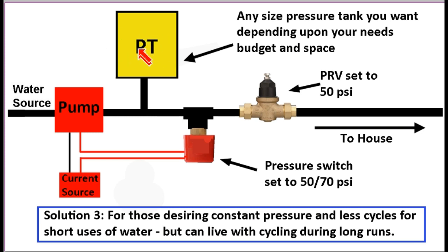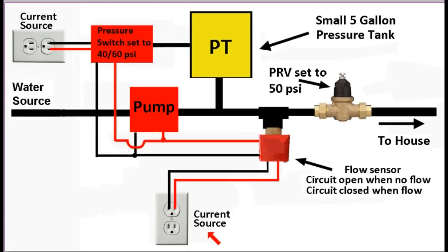Now with this system, you can have a large tank without any penalty, because when the water stops being used, the pressure tank will be filled up at the full rate. There's no dribble flow. And when you start using water again, you don't have this long period of unstable pressure. The pressure starts at 50 immediately and stays at 50 for the rest of the time, which does not happen with a cycle stop valve. And in particular, a cycle stop valve with a large pressure tank would cause you to have very unstable pressure at the beginning of the run before it stabilizes. Okay, so this is solution 4.